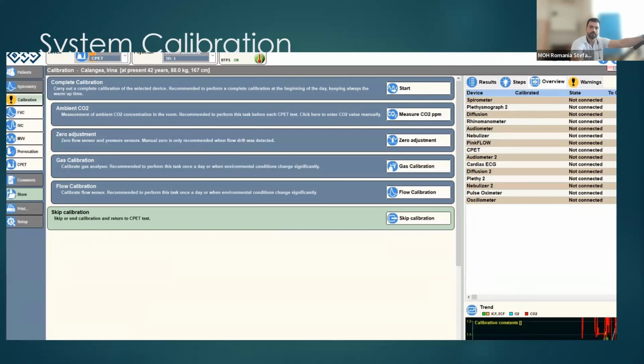Nowadays, as the BTL system also has, all the modern cardiopulmonary exercise systems contain rapidly responding oxygen and carbon dioxide sensors that allow for the calculation of the oxygen uptake and carbon dioxide output at rest, during exercise, and during recovery, as frequently as breath by breath. Normally, the cardiopulmonary systems, as I said to you, should be calibrated immediately before each exercise test. I would mention to you that, unfortunately, we don't have the time to do this step as recommended by the guidelines. We only do the calibration at the beginning of the day, because there is a step where you need to ventilate the room. Afterwards, you need to start the analyzer and leave it for 30 minutes in order to calibrate.